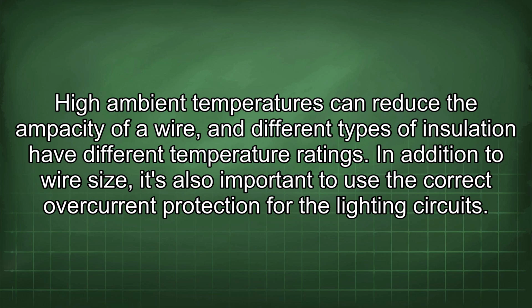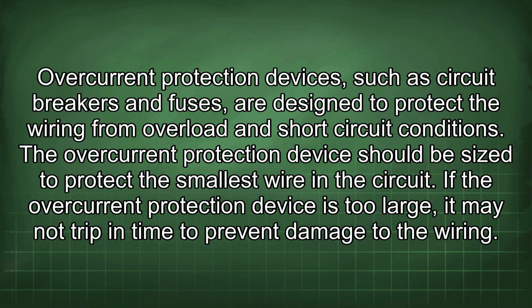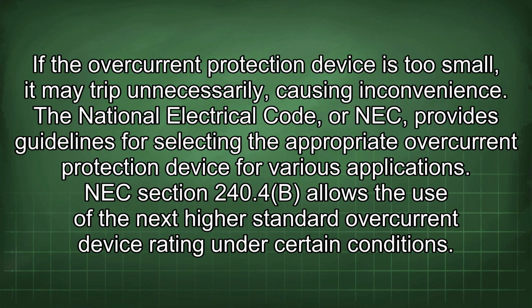In addition to wire size, it's also important to use the correct overcurrent protection for the lighting circuits. Overcurrent protection devices, such as circuit breakers and fuses, are designed to protect the wiring from overload and short-circuit conditions. The overcurrent protection device should be sized to protect the smallest wire in the circuit. If the overcurrent protection device is too large, it may not trip in time to prevent damage to the wiring. If the overcurrent protection device is too small, it may trip unnecessarily, causing inconvenience.